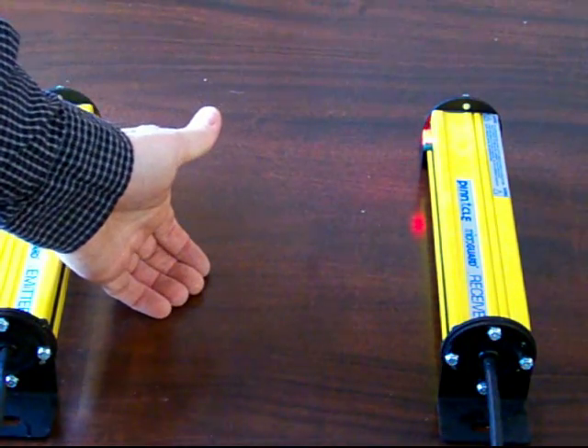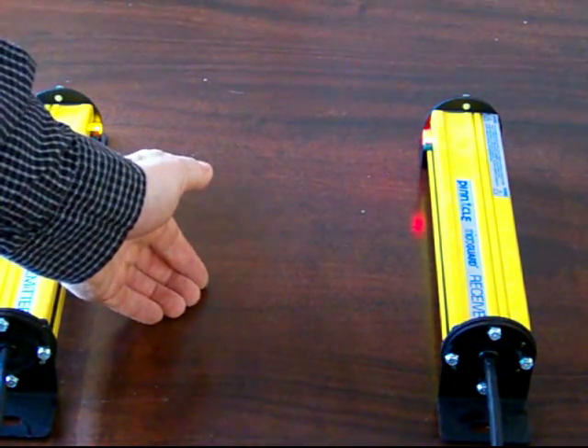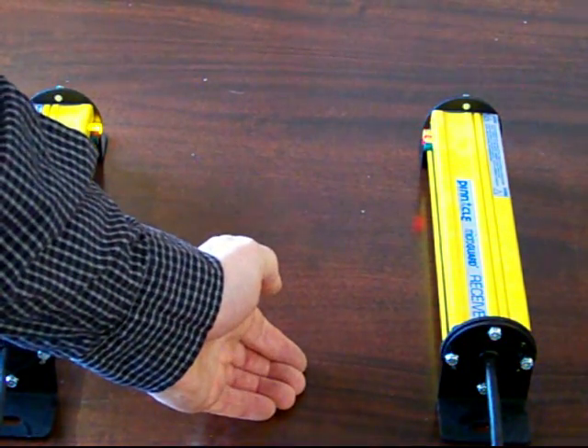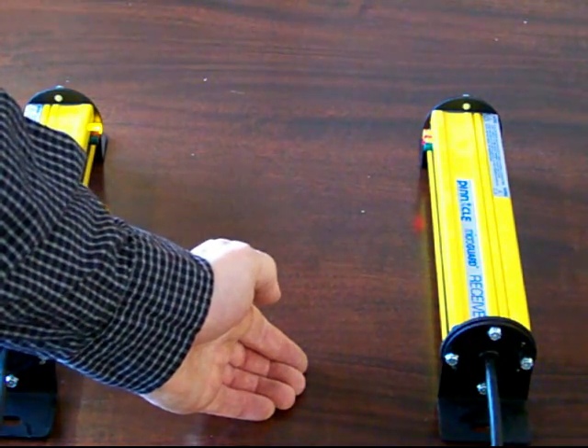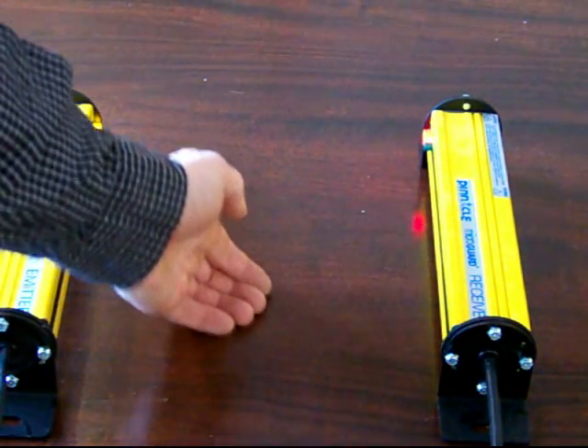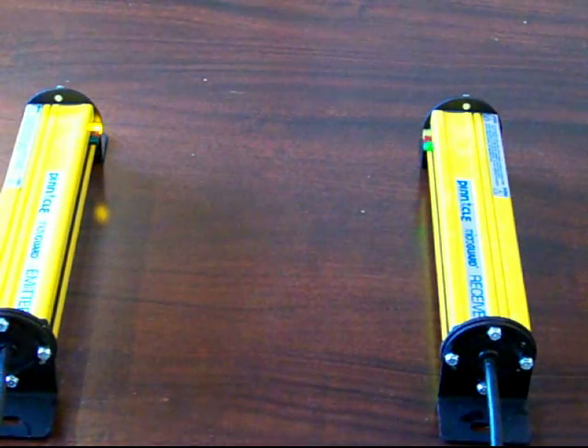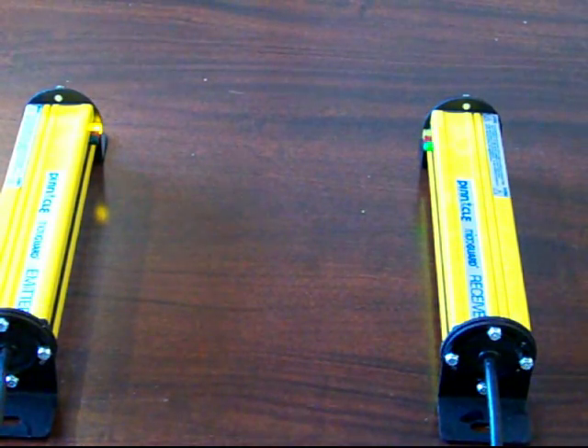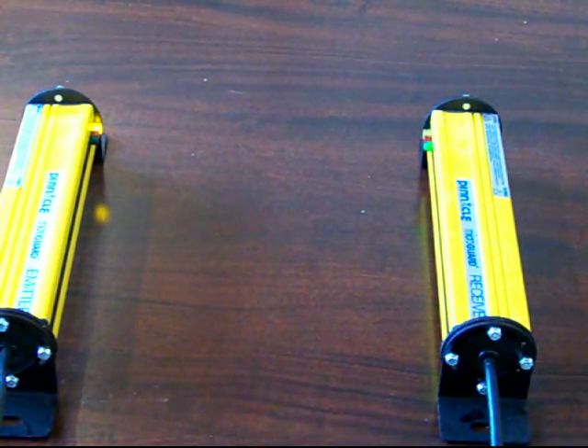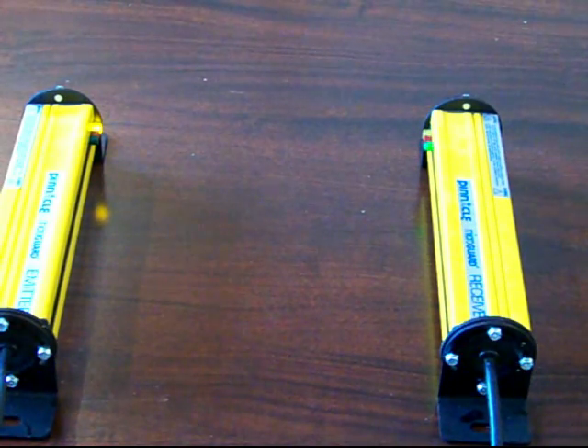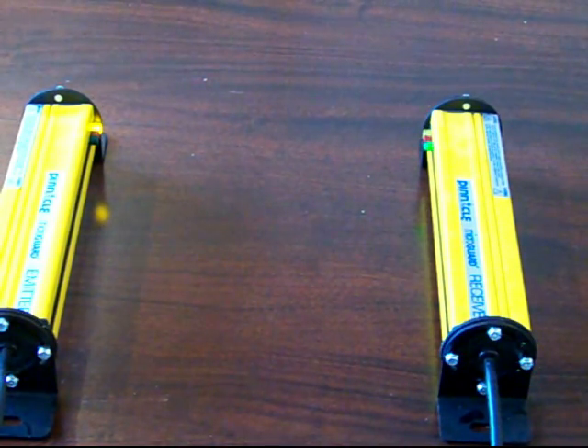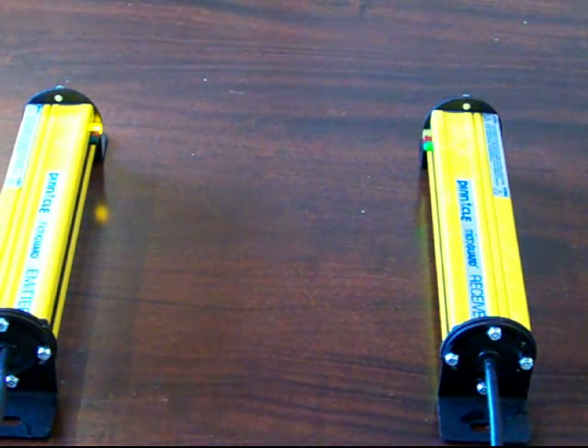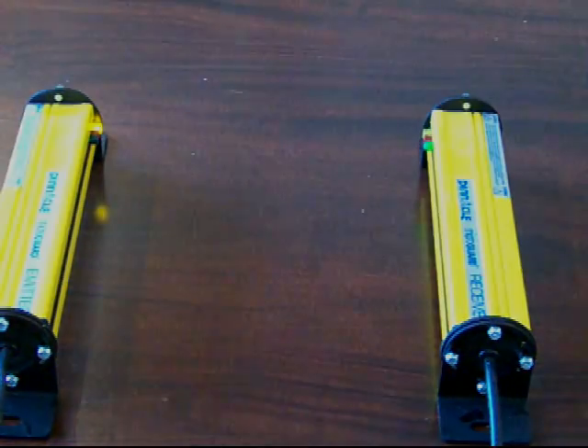It's green when it's not blocked. It gets bright red when you're blocking it. And if the sync beam, the last beam, is blocked, it gets a dim red. So you get dim red when you're blocking the bottom beam, bright red when you're blocking any of the other beams. You take your hand out, the unit goes back green. The emitter side stays yellow with that blinking red just to let you know that it's alive and operating. This allows you to free up the emitter side. Now the emitter side can be powered from a different power source instead of together with the receiver side.